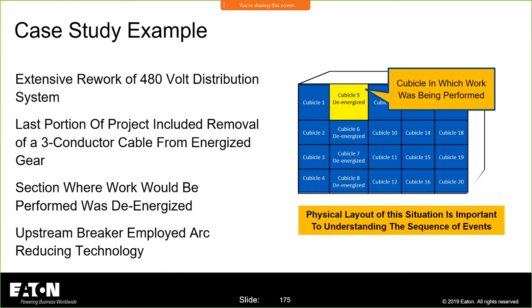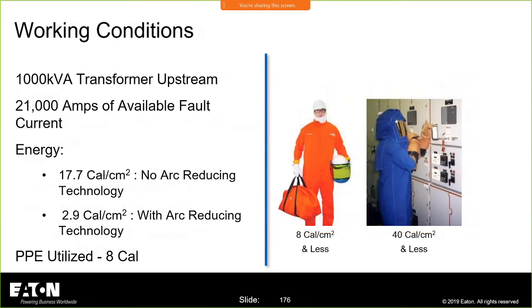They followed all of the rules when it comes to 70E work practices. They had the pre-job planning and all of the things that they should do. They knew they had 1,000 kVA transformer upstream, 21,000 amps of available fault current. Without an arc reduction technology that we have as a requirement in 240.67 and 87, they were using the arc reduction maintenance switch here. It would have been 17.7. So in this plant, they were either going to dress for a 40 cal or an 8 cal. That's just how they trained everybody, and that's what they did.